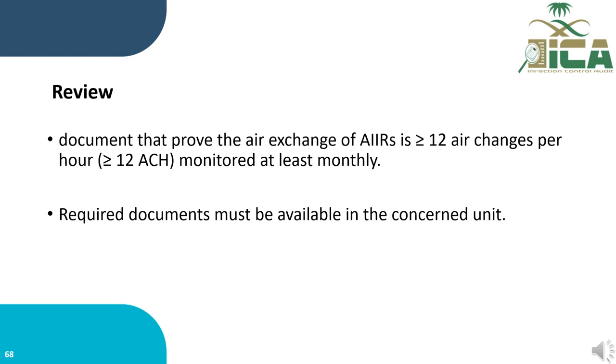It's not acceptable if they say it is only with the maintenance or biomedical department. They should have a copy of this monitoring for the air change per hour, and they should keep it inside the department, and it should be 12 or more air changes per hour.